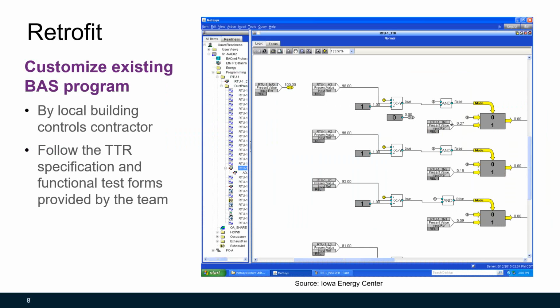Again, the retrofit mostly involved customizing the existing building automation system program. The customization of these control programs was done by local building control contractors following the tiered trim response specification provided. The research team also provided a functional test form to these control contractors. The control contractors needed to follow the functional test forms to make sure the control sequences were programmed and implemented correctly. Here is an example of a portion of the tiered trim response method program.